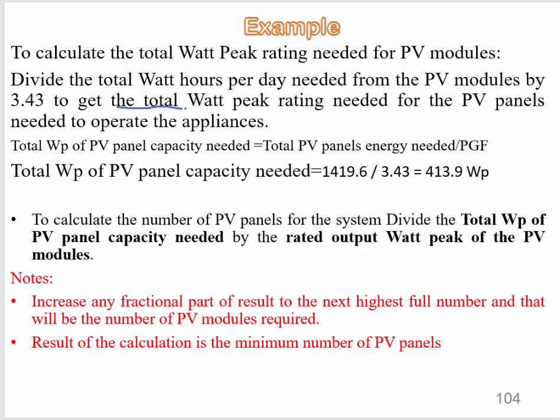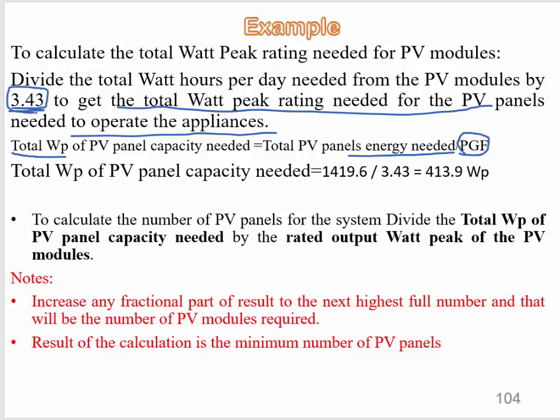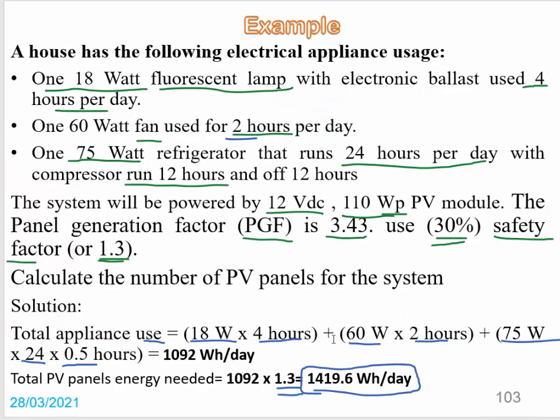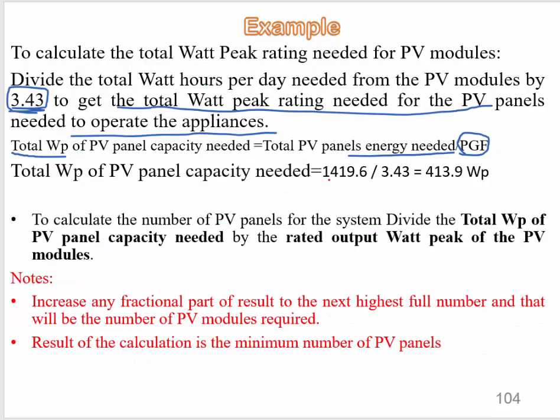Now to calculate the total watt peak rating needed for the PV panels, we apply the formula: total Wp of PV panel capacity needed equals the total PV panel energy needed divided by the panel generation factor (PGF). With PGF = 3.43 and total energy = 1419.6 Wh/day, dividing gives a final result of 413.9 watt peak.